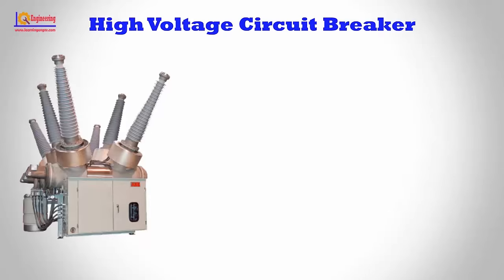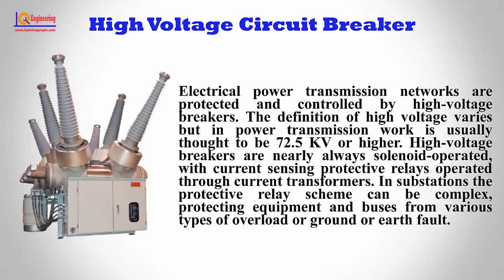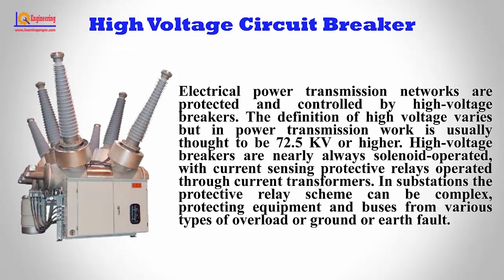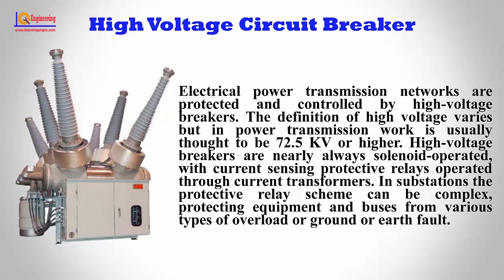High Voltage Circuit Breakers protect and control electrical power transmission networks. The definition of high voltage in power transmission work is usually considered to be 72.5 KV or higher. High voltage breakers are nearly always solenoid operated with current sensing protective relays operated through current transformers. In substations, the protective relay scheme can be complex, protecting equipment and buses from various types of overload or ground/earth fault.